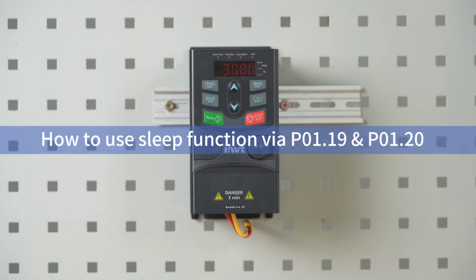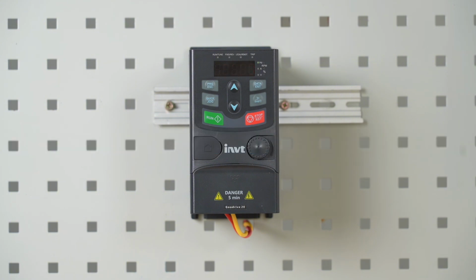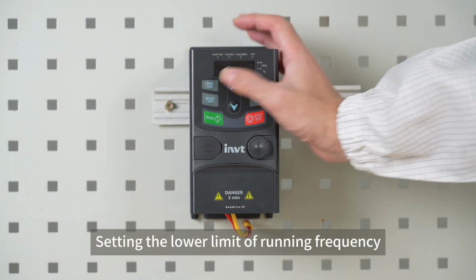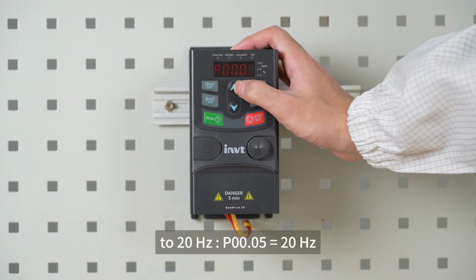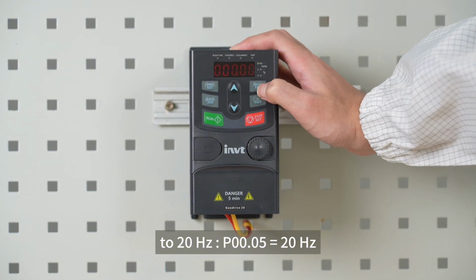How to use sleep function via P01.19 and P01.20. Setting the lower limit of running frequency to 20 Hz, P00.05 equals 20 Hz.